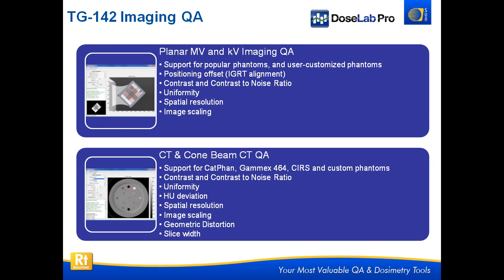We also have a full imaging QA suite. In addition to all your machine QA, you get all of your OBI or KV QA, Conebeam CT, and MVCT — we're compatible with all of those. For our planar MV and KV imaging QA, we support a lot of popular phantoms. SunNuclear has their own phantoms, and we also support standard imaging phantoms, the phantoms that come with your machine, the Leeds phantom, the Las Vegas phantom. You can even add your own if what we have is not in the list.